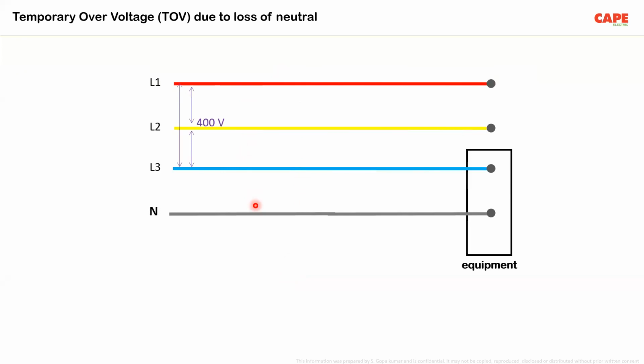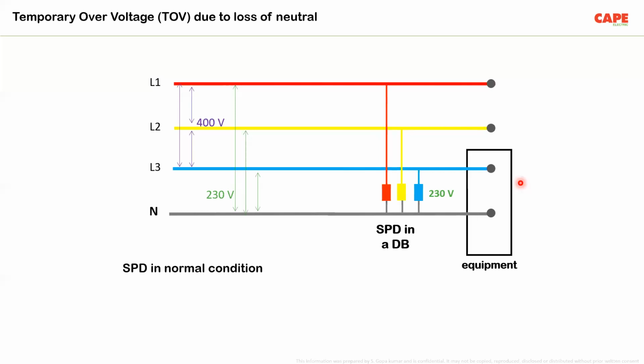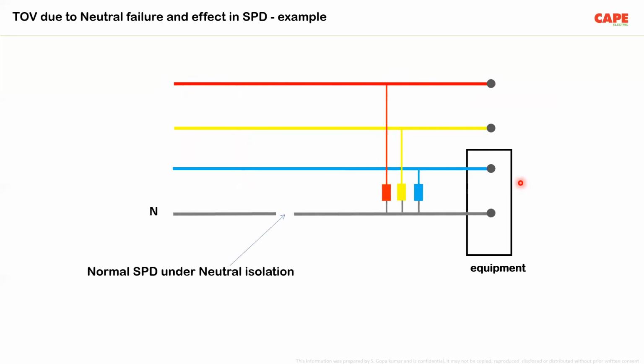Now, between the lines, you have 400 volt, and between the lines to the neutral, you have 230 volt. But imagine here you have a single phase equipment connected. We have three SPDs connected between line and neutral. So in normal condition, everything is perfect. Imagine a situation when there is a neutral disconnection. What is neutral disconnection? Very simple. The neutral wire has just broken.